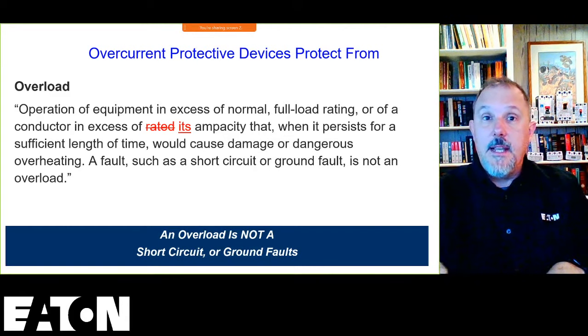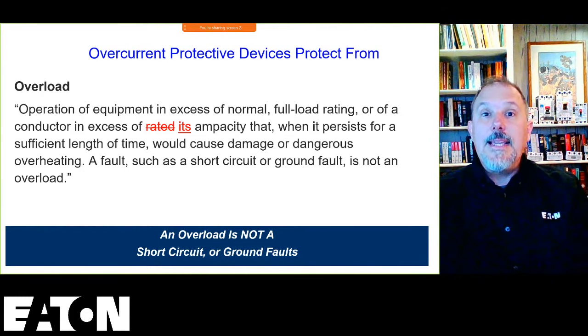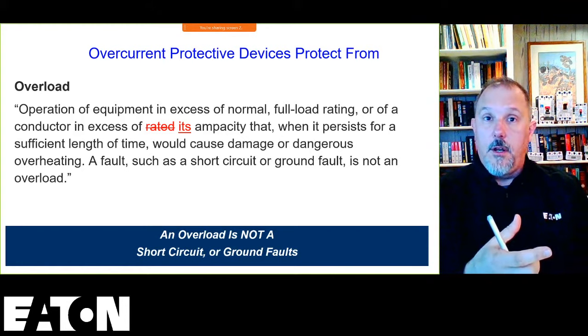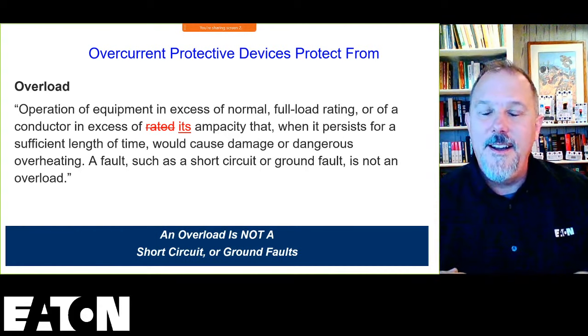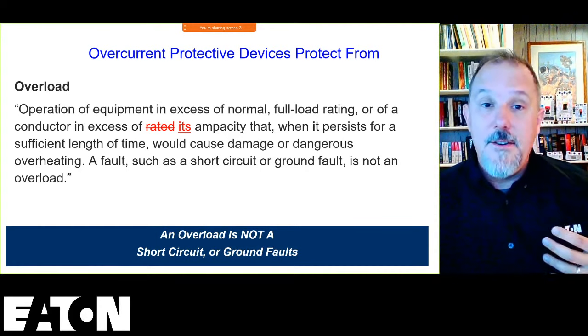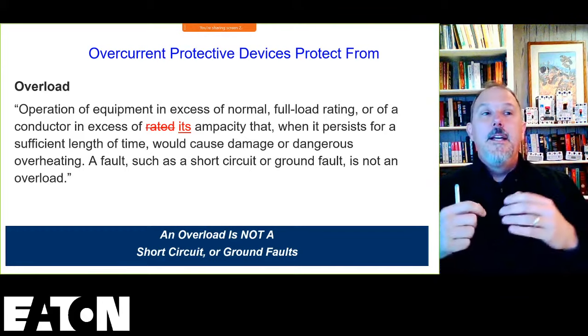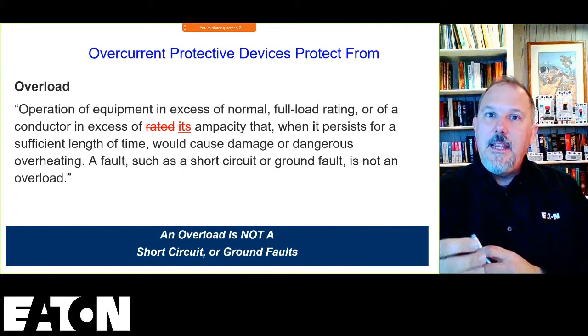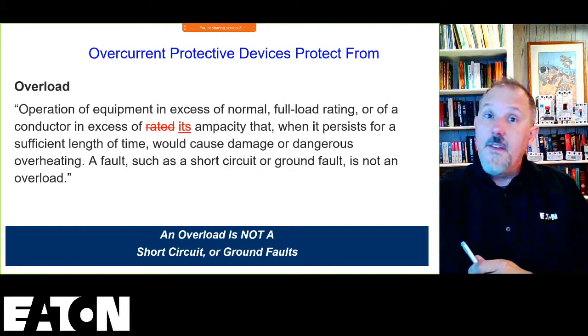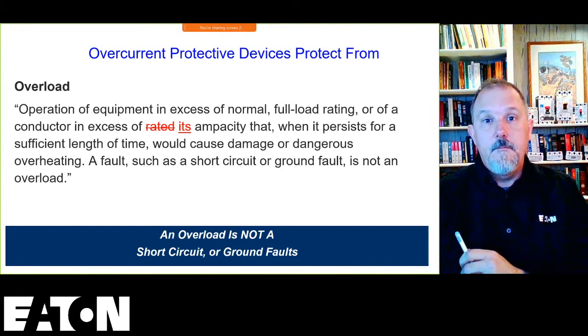And if it persists, well, I can live with an overload. We talked about how it takes like 1 to 6 hours for me to heat up a conductor over time. I can live with short durations of overload. If I have a motor on a rock crusher or a motor driving a conveyor belt that I'm standing on, or a treadmill that I'm standing on, it's going to pull higher currents than full load amps. I may exceed the ampacity of a conductor for short periods of time, perfectly fine, because I'm not going to generate enough heat to damage the insulation, since it's not persistent long enough.